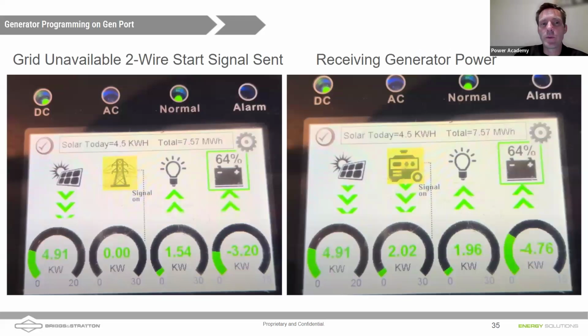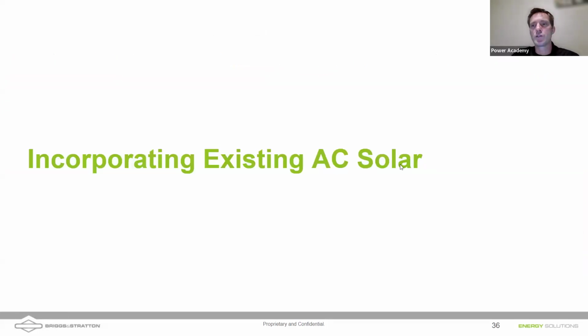Let's suppose the grid is down and this is calling for a generator. It's either the grid that is active on that AC bus or the generator. You can't have grid and generator active at the same time. Right, we don't have any grid-following generators to my knowledge. On the grid icon here, you'll see a two-wire signal to start going down, shown as a dashed line on your screen. Then, if the generator starts up and the signal is qualified by the inverter, it turns into a generator and you can see power flow coming from the generator. You'll see that on the front screen. That's a nice feature, letting you know that you're using generator power.